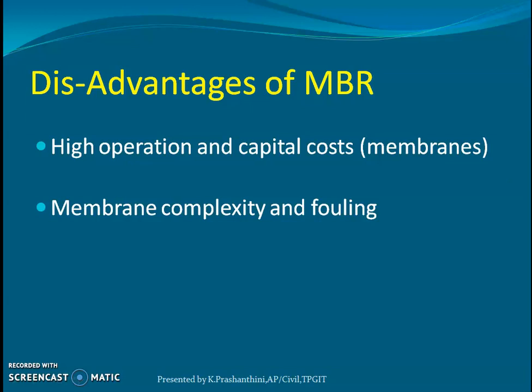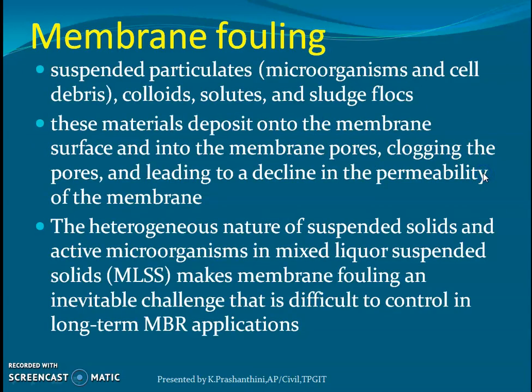The disadvantages of MBR include high capital and operational costs due to the membrane. The major drawback is membrane fouling, which is the clogging of filters due to suspended particles in the bioreactor, including microorganisms, cell debris, colloids, solutes, and sludge flocs. On continuous operation, these suspended particles completely clog the membrane and render it non-functional.